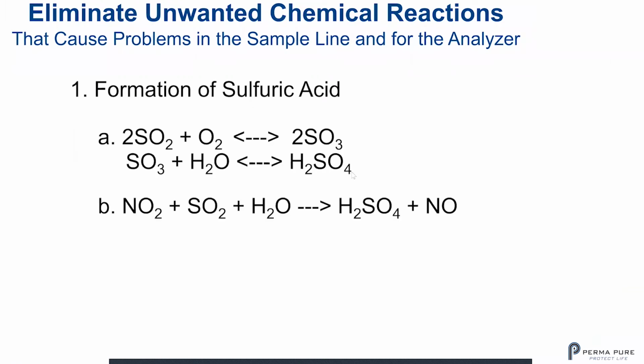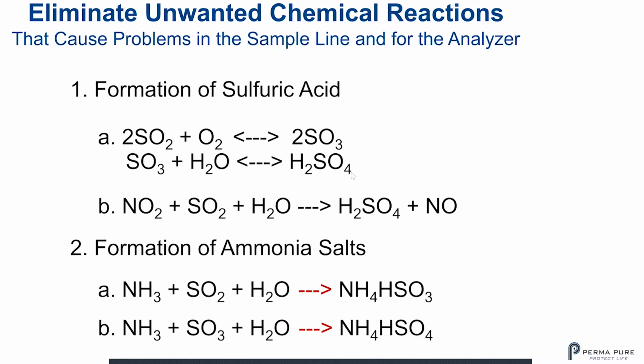So here's a couple of unwanted chemical reactions that we can eliminate here. The first is the formation of sulfuric acid. These cause problems in the sample line up to the analyzer. This is where you have your SO2 plus oxygen combine to form 2SO3. When you have SO3 and water together in the vapor phase, you can get H2SO4, sulfuric acid. This is very important. This is what we reduce when we reduce the vapor in the gas stream.